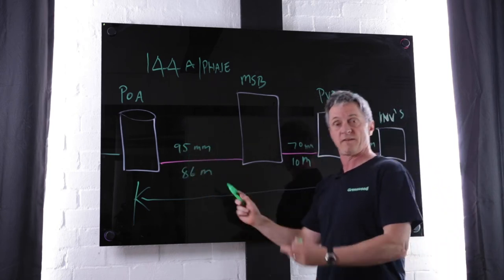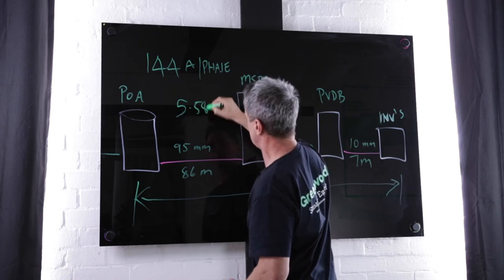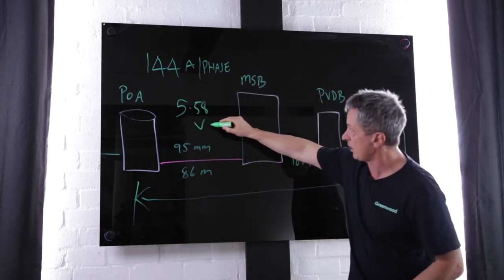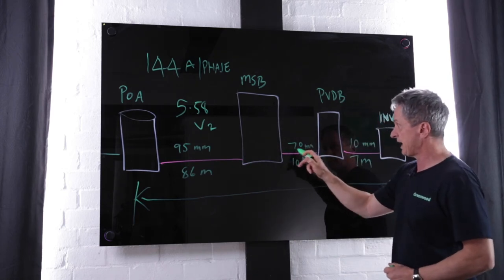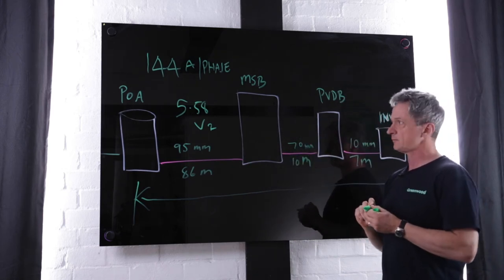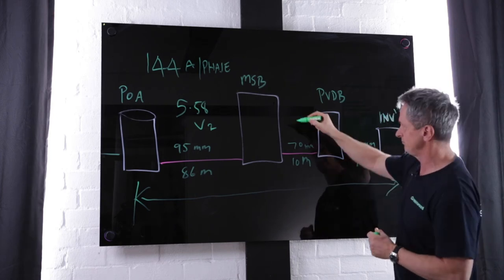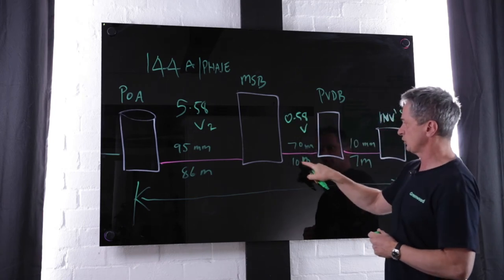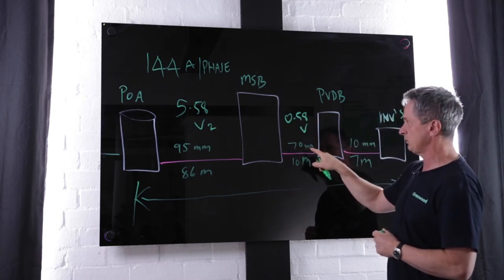Doing that, we found the volt rise was 5.58 volts for that section. For the short run — 10 metres using 70mm² cable — the calculation came in at about 0.58 volts.